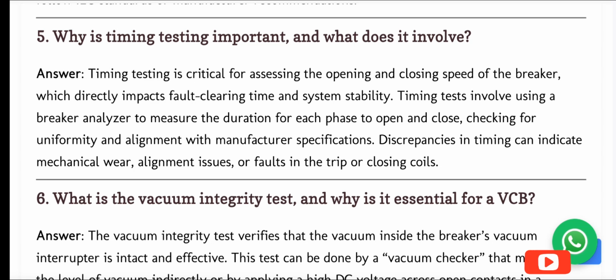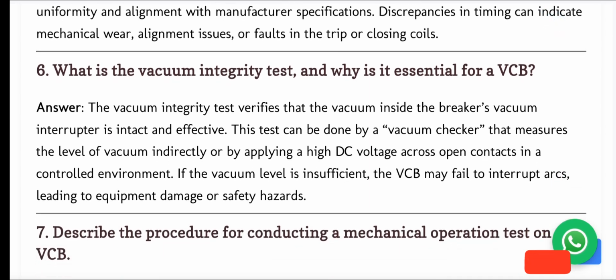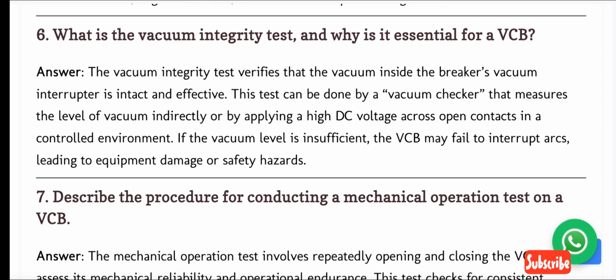Answer. Timing testing is critical for assessing the opening and closing speed of the breaker, which directly impacts fault clearing time and system stability. Timing tests involve using a breaker analyzer to measure the duration for each phase to open and close, checking for uniformity and alignment with manufacturer specifications. Discrepancies in timing can indicate mechanical wear, alignment issues, or faults in the trip or closing coils. 6. What is the vacuum integrity test, and why is it essential for a VCB?